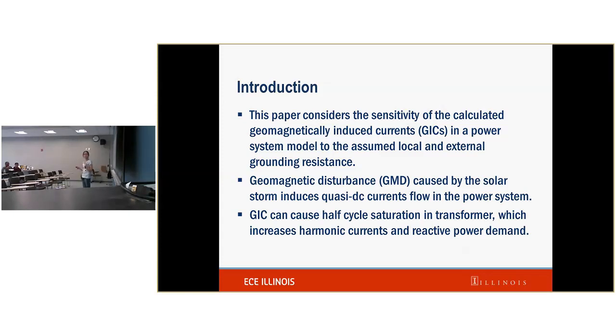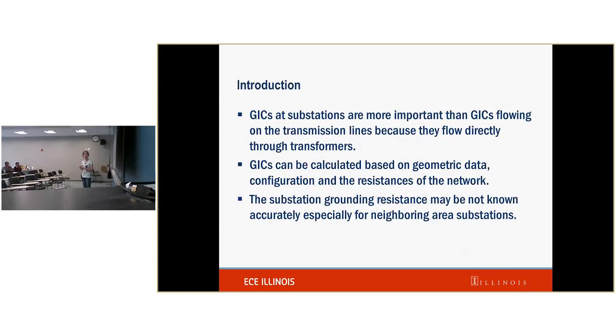Let me introduce something about GIC and why we have GIC in the power system. Geomagnetic disturbance is a phenomenon caused by a solar storm, and it induces a quasi-DC current flow in the power system. This quasi-DC current can cause half cycle saturation in transformers, and it results in harmonic currents and increased reactive power demand. I focus more on GIC at the substation because this GIC flows directly to the transformer, hence it causes the most damage. The GIC can be calculated based on the topology of the system, the resistance of the transmission line and transformer, and the resistance of the substation grounding.